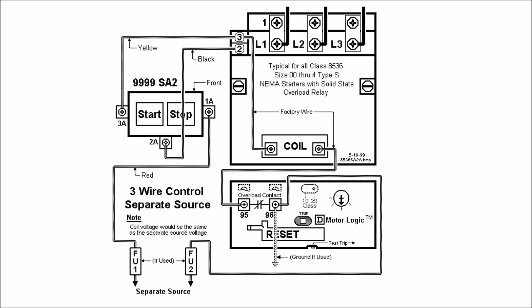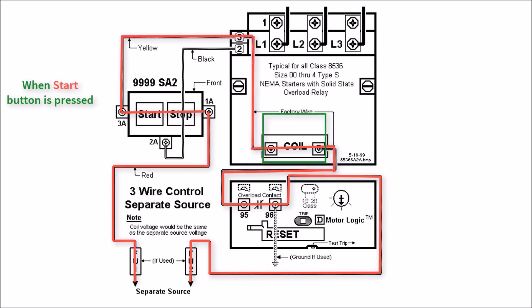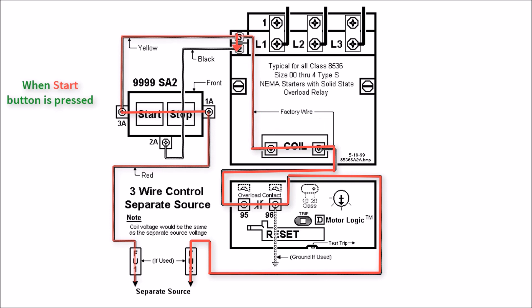So what happens when you hit the start button is your 1A to 3A closes sending power here to terminal 3 on your holding circuit engaging the coil and then when this coils engage this holding circuit contact actually closes.